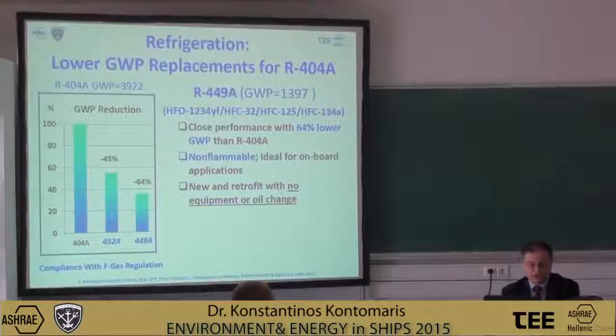But although those were the objectives, the primary objective in formulating this fluid was to reduce the GWP while maintaining close performance with 404A. However, the new fluid, as a bonus, achieves substantially higher energy efficiency as well. The energy efficiency relative to 404A, the incumbent fluid, is improved by 8 to 12% under medium temperature refrigeration, which is, say, up to -10, -15 degrees Celsius, and about 3% improvement in efficiency for lower temperature refrigeration conditions, we say -35 degrees Celsius, -40 in that range.